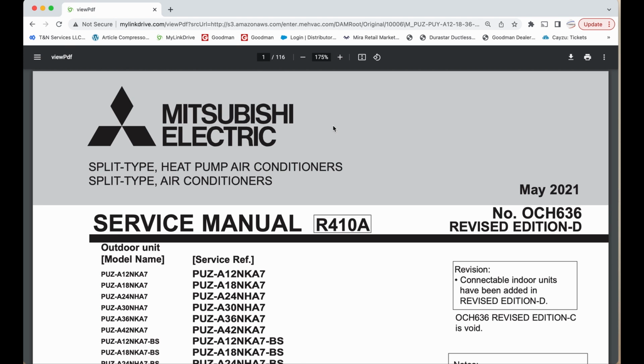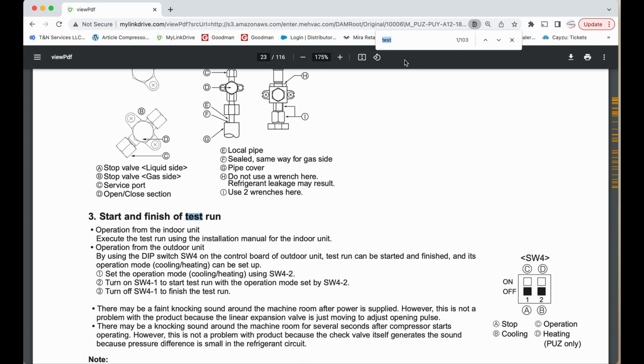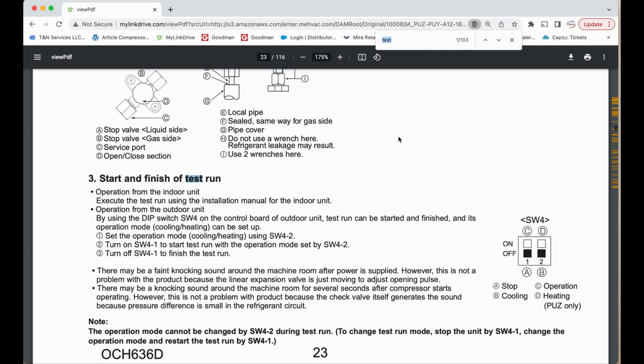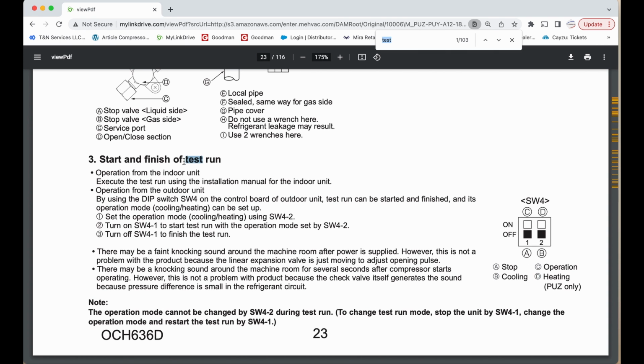And then we're going to do our Command F, our Control F, and it gives us 103 choices. So we're just going to click here. The very first choice we have actually takes us to the right place. So start and finish the test run. So on a P series, it's SW4. So that bank of dip switches, there's only 2. So if you were in the cooling mode, all you would have to do is turn SW4-1 on and that would put your unit in test run in the cooling mode.